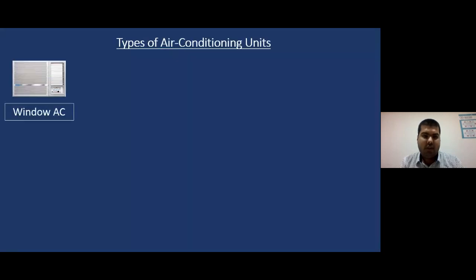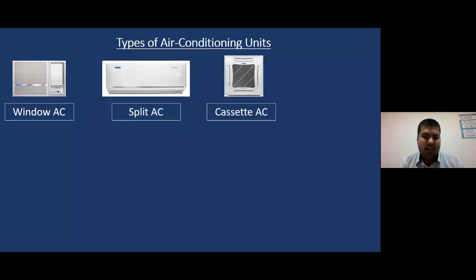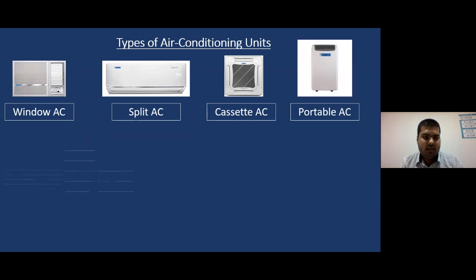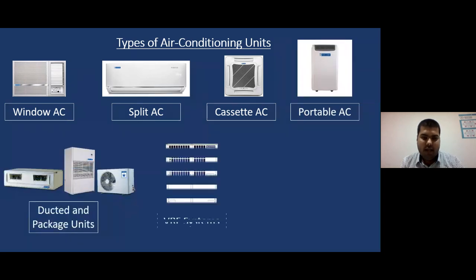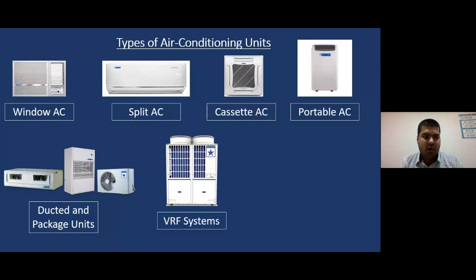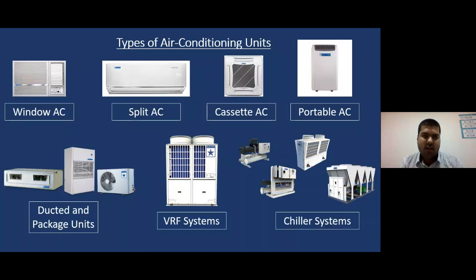Now, on the types of air conditioning units, I would just highlight what products the air conditioning industry has: window AC, split AC, cassette AC, portable AC, ducted and package units, VRF systems, and chillers. What started the air conditioning industry was the window AC, and today we have much more developed VRF systems, chillers and ducted units. A window AC would have a nominal capacity of 1 ton, and a chiller at max goes to a single machine of 4,000 tons. So that is the huge range which air conditioning can handle.